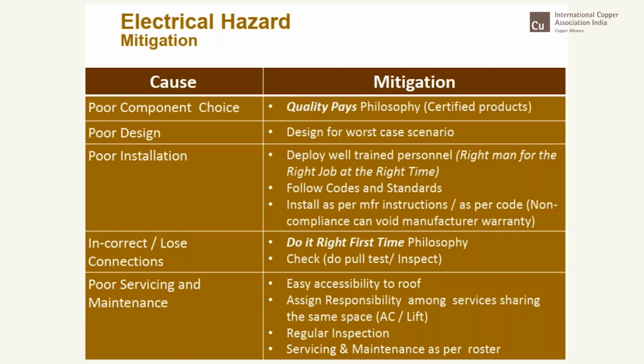level itself. And then poor design, for example, the same ampacity of the cable, that is again a poor design. Poor installation: if you don't have properly trained people and they don't follow any codes, they are not aware of the consequences. And many times we may be perfect specialists in all the technology, but every manufacturer has his own way of expecting us to manufacture. So many times, even in our own personal life, every equipment that we buy comes with a user's manual. We never read that.